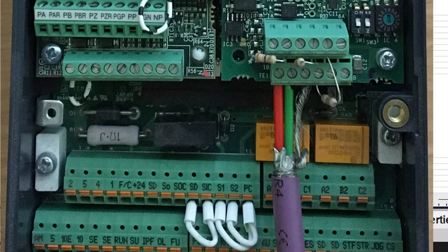The red wire needs to be connected to terminal 1B, the green wire needs to be connected to terminal 2B, and the shield needs to be connected to terminal 3B. Both ends of the network need to have terminating resistors.